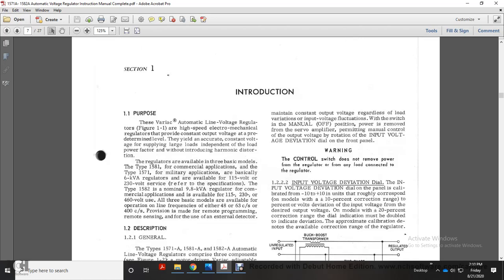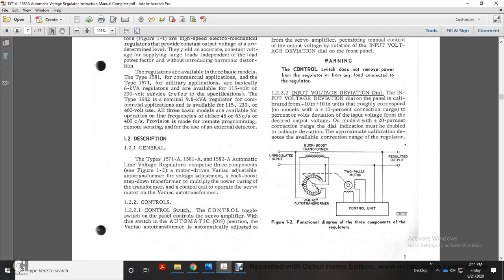1-2-2, input voltage deviation dial. The input voltage deviation dial on the panel is calibrated from negative 10 to positive 10, in units corresponding to percent of the voltage deviation of input voltage from desired output voltage. On ranges with plus or minus 20 percent correction range, the dial indication must be doubled to give the deviation. Approximate calibration denotes available correction range of the regulator.